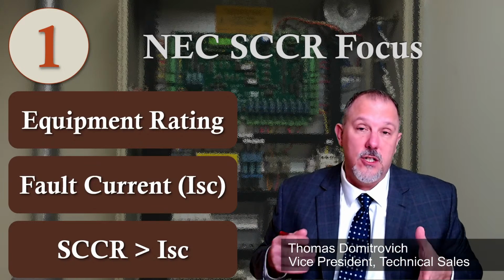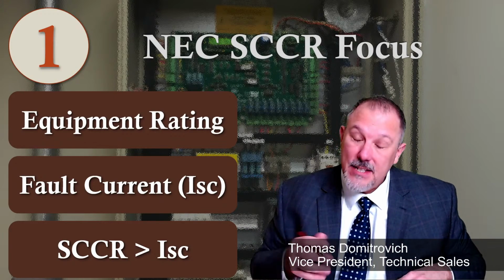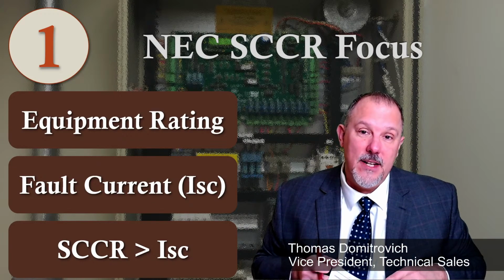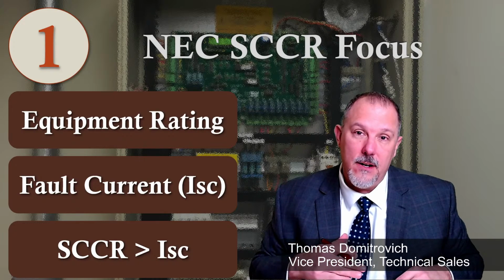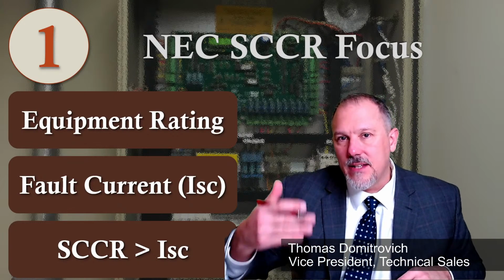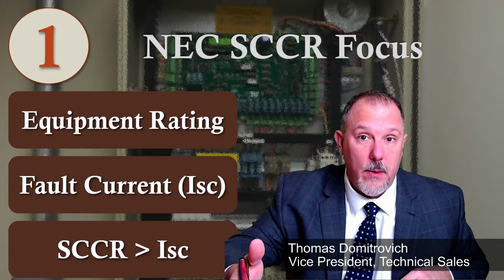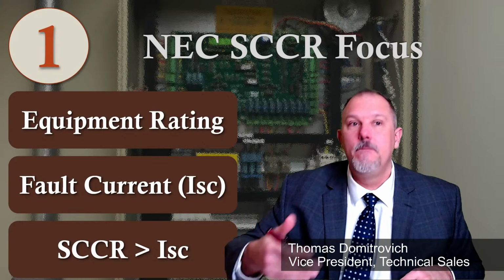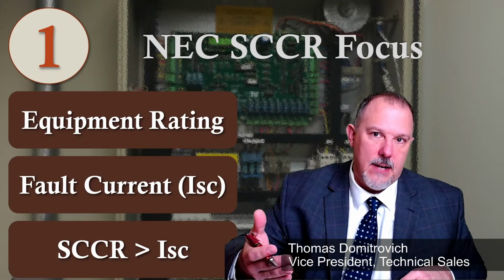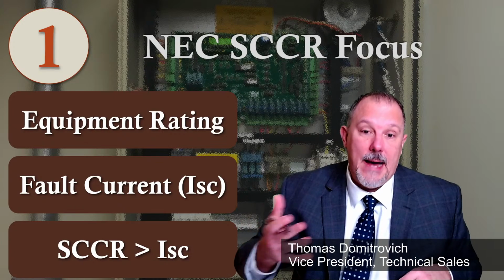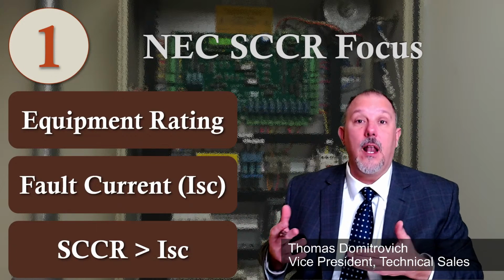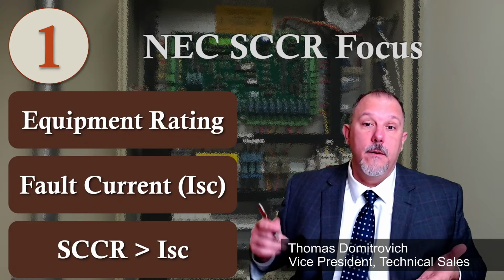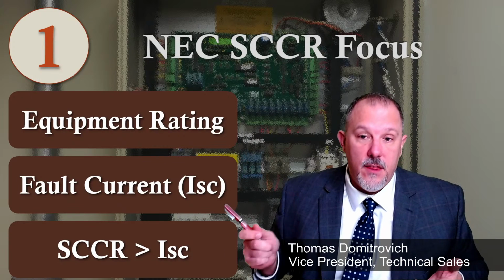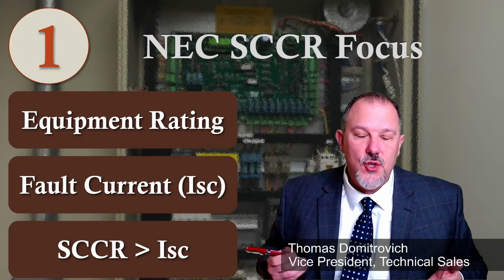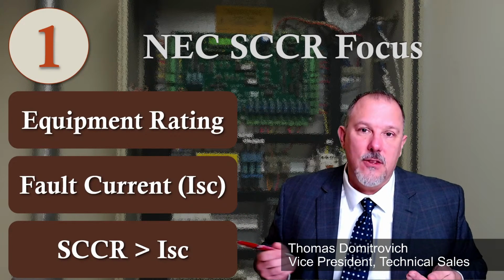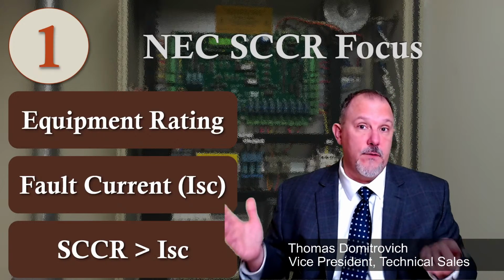There's a lot of great reasons to use busway. The challenge is the fault current at the top of that building is not knocked down very far, and now you have an elevator control panel or HVAC equipment at the top of that building, and the fault currents are greater than 10,000 amps. And now what's happening in the code is a level of awareness for the rating of the equipment and the available fault current, to make sure that your fault current is less than the rating of the equipment. It's important for safety.